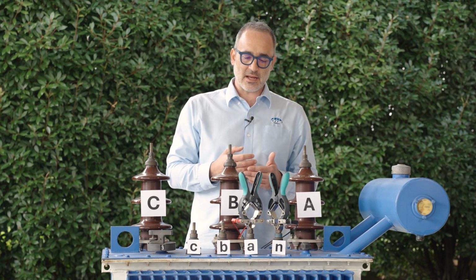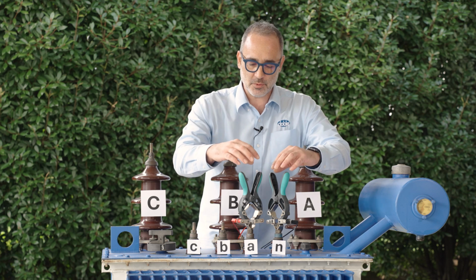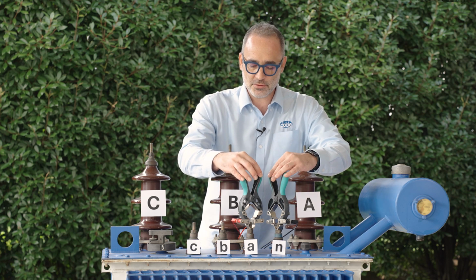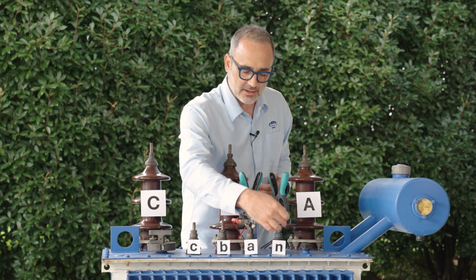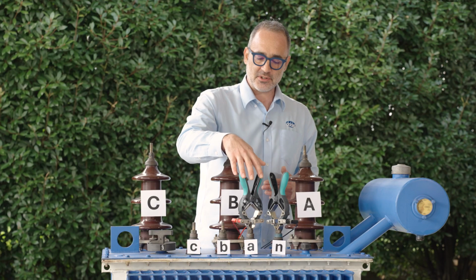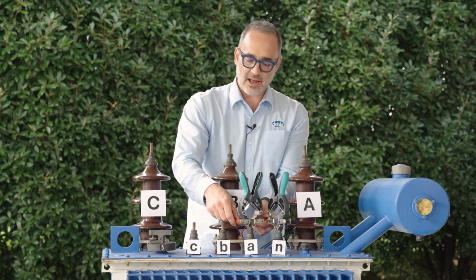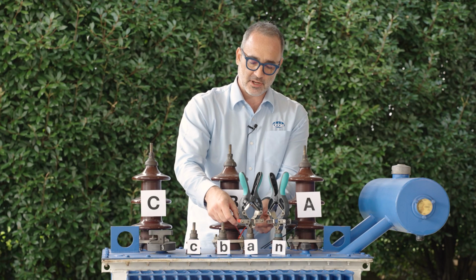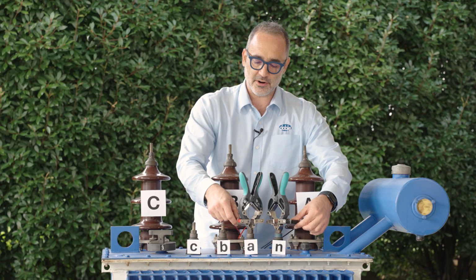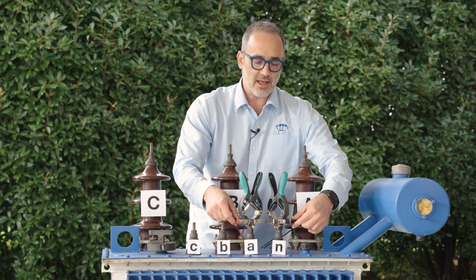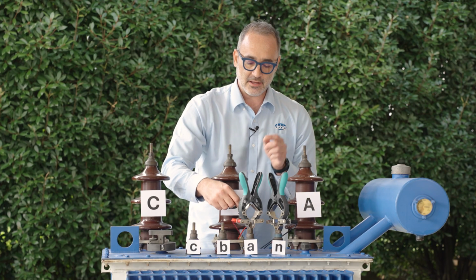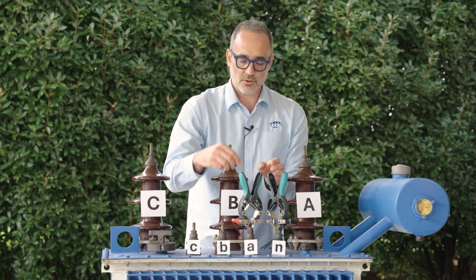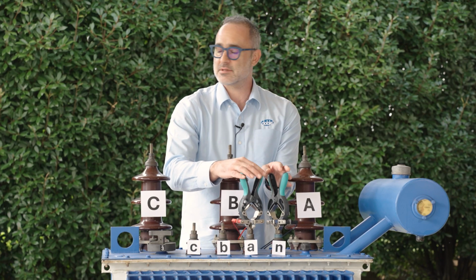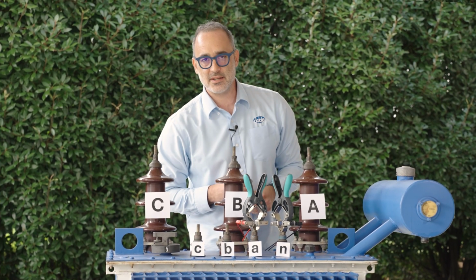So let us now, having connected between phase A and neutral, measure the winding of phase A of the secondary side. Here I have connected the input of the current and the output of the current. Let's say current is coming in here and leaving through here, and the voltage measurement. So having connected like this, let's move on to the STS to do the test.